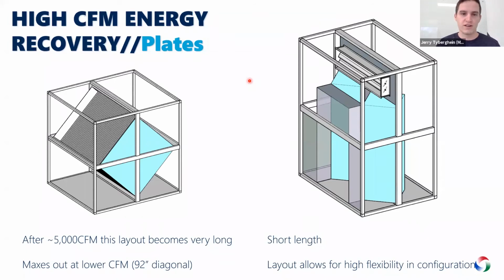But real quick, before I get into that, I do want to go over a concept that we utilize all the time. On the left is a plate heat exchanger. You've probably seen this before. It's one big diamond, but that limits you because once you get to a certain CFM, over maybe 5,000 up to maybe 10,000 at max, you start to get too long because you can only increase that diamond size and then you can't ship it anymore.